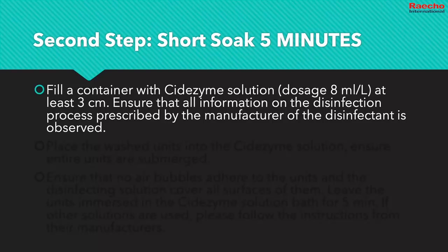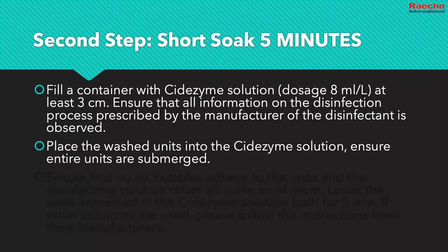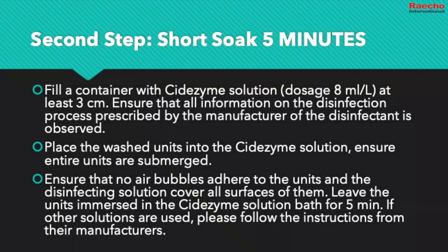Fill a container with Cidezyme solution at least 3 centimeters deep. Place the washed probes into the Cidezyme, ensuring that the probes are completely submerged and that no air bubbles are sticking to the surface of the probes, and that the disinfecting solution covers every single surface of the probe.